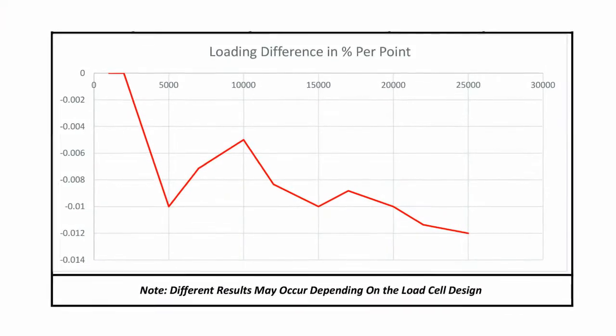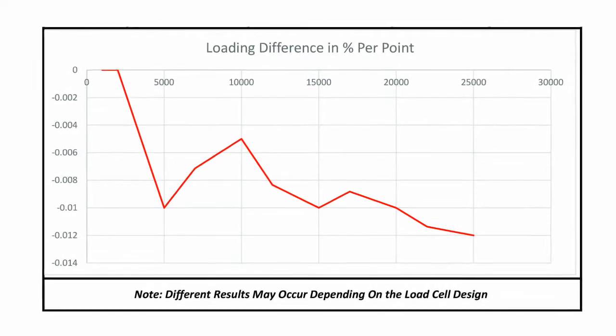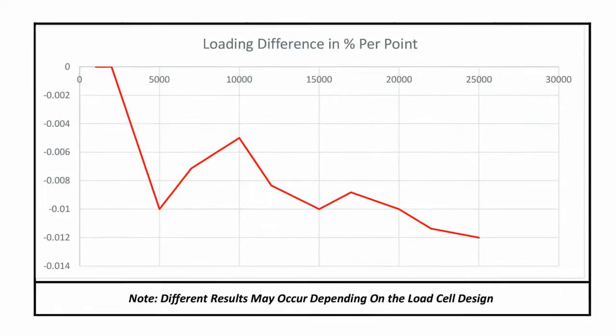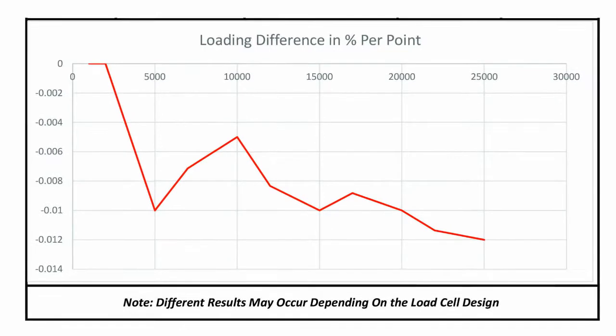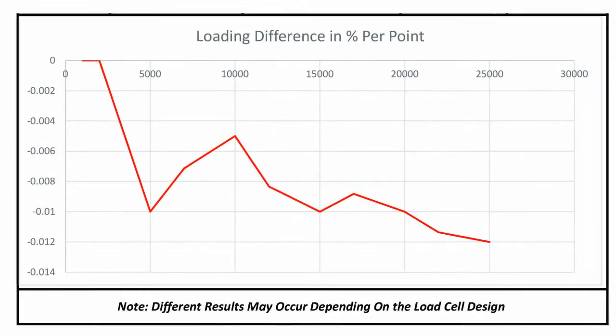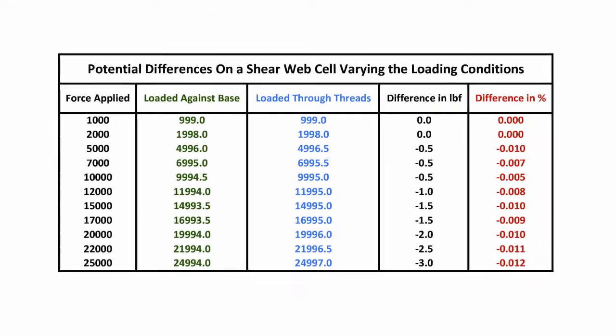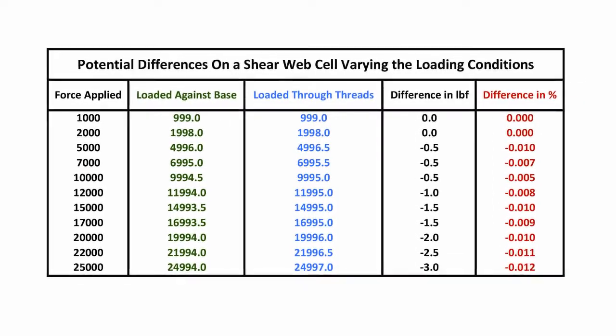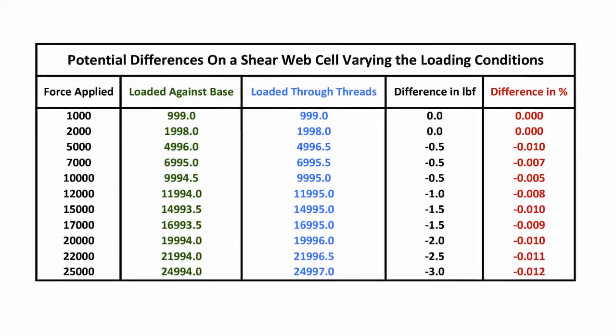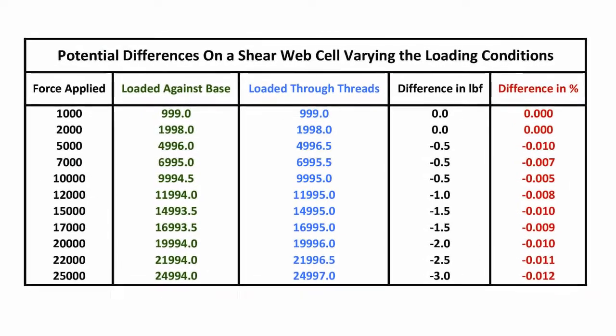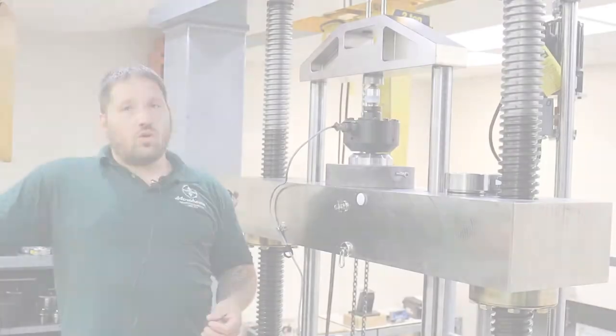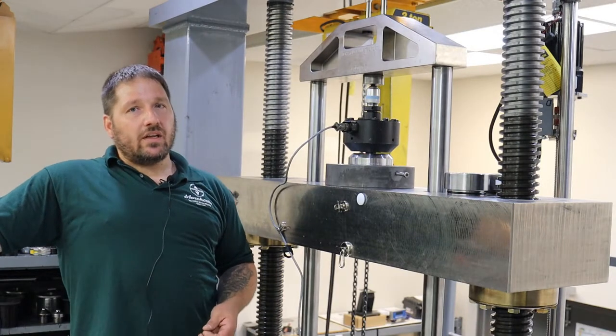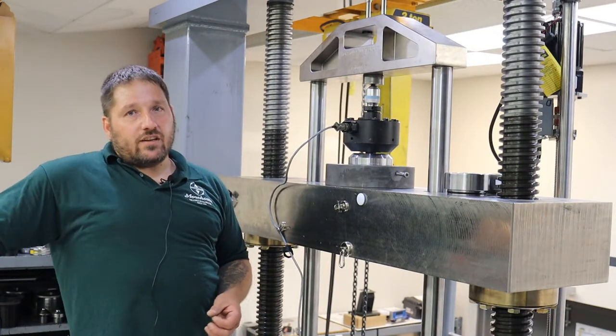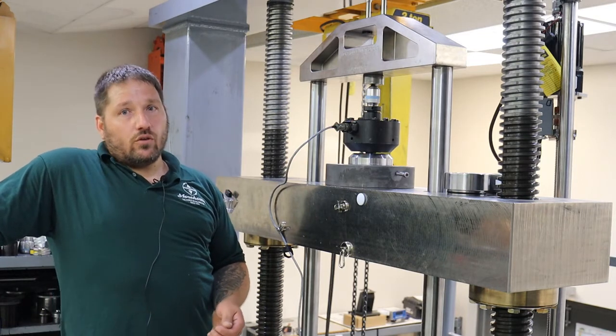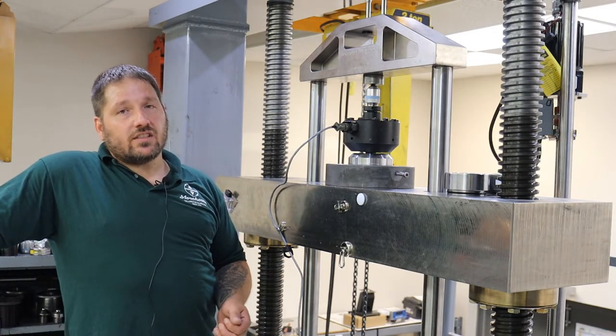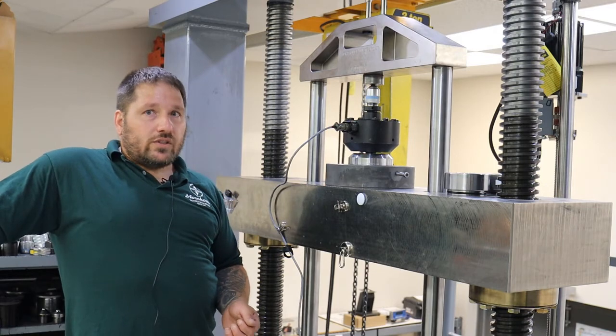So here's a graph showing the results of a shear web load cell we tested. These are very good load cells, and depending on the difference in the type of load cell or your loading conditions, your results really could vary. As you can see on this one, it's a 0.012% difference between the different loading conditions. The most important thing is to replicate what you do all the time and make sure your calibration company knows all the information they need to know on how you load your load cells, so we can be very consistent with the results that we give you.